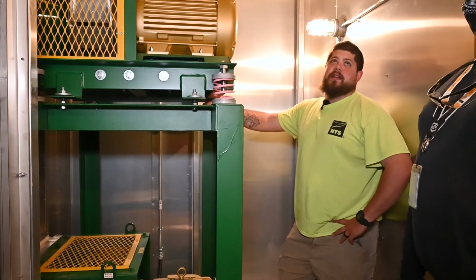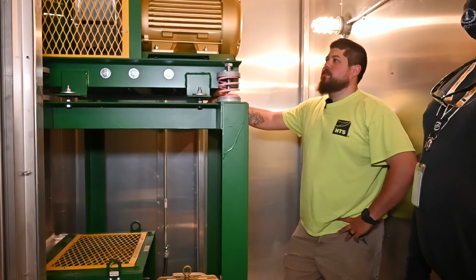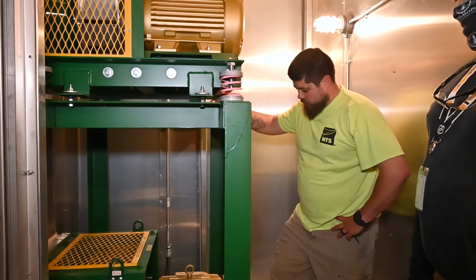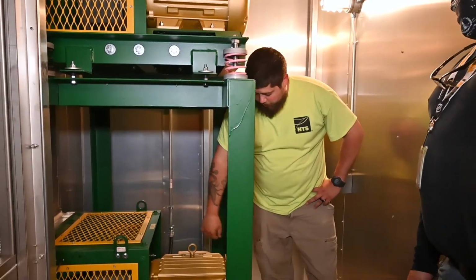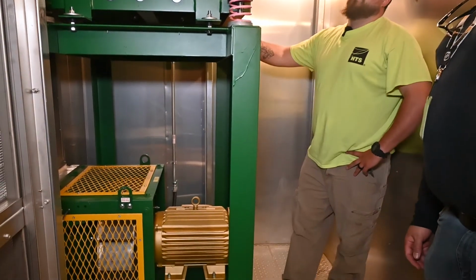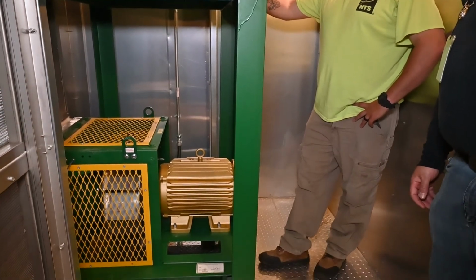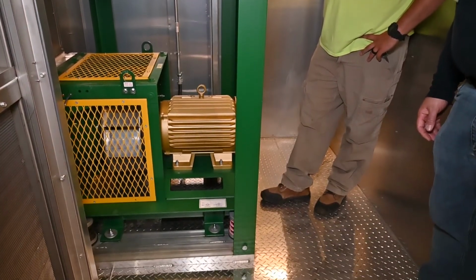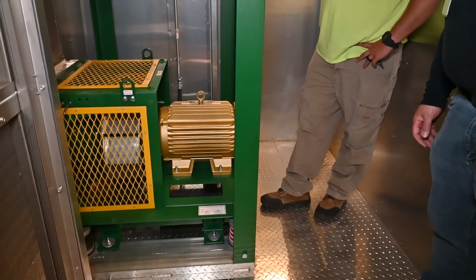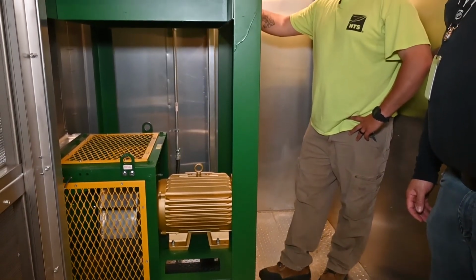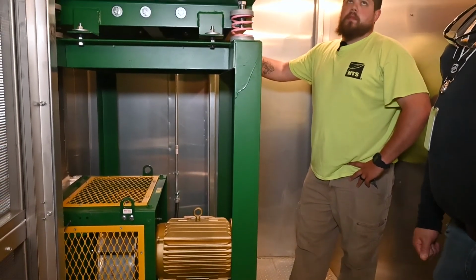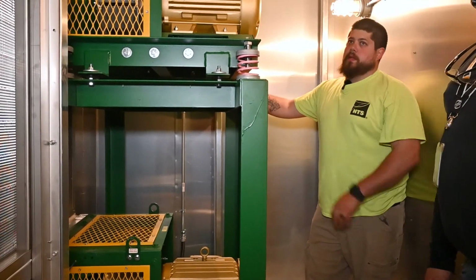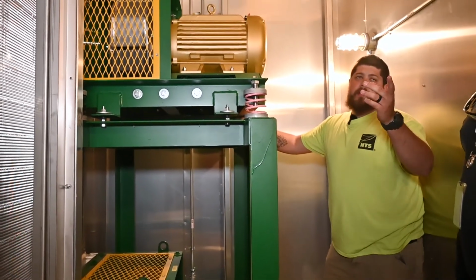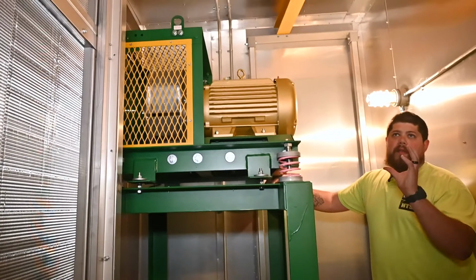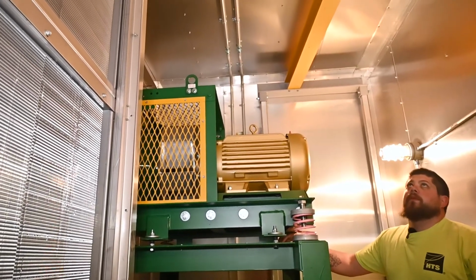So this is the supply fan section. You have 2 direct drive motors. They do have 2 greasing spots right here, the motor itself and the bearing up front. We recommend greasing those roughly every 6 months during the maintenance that gets done to the unit. You've got 2 DPs there, which you saw earlier. Those run outside. There's a coil controller that'll show when we go out there that's displaying what the CFM of the unit is, what's going on.